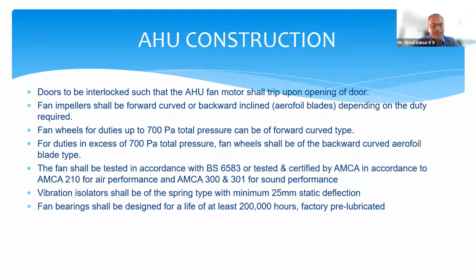Now the fan has to have bearings, obviously. These bearings are supposed to be fully sealed for life bearings and at least able to run for 200,000 hours, or 2 lakh hours of running hours, because if you check with your technicians, they would be changing the bearings every now and then because there is a noise issue, there is a load issue. Now, why is it? Because the fan bearings have not been selected correctly. So if you have a spec like this in your tender, you will make sure that the AHU comes with fan bearings which are long life. That's very important.